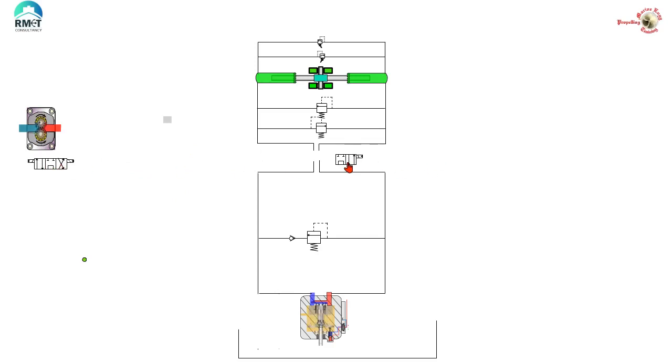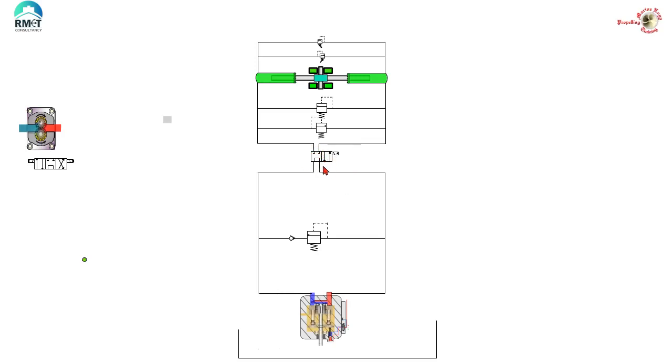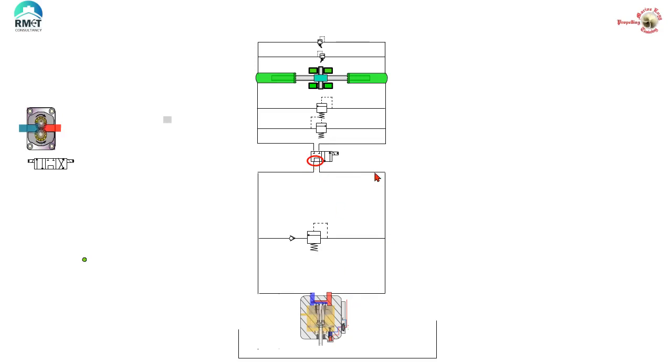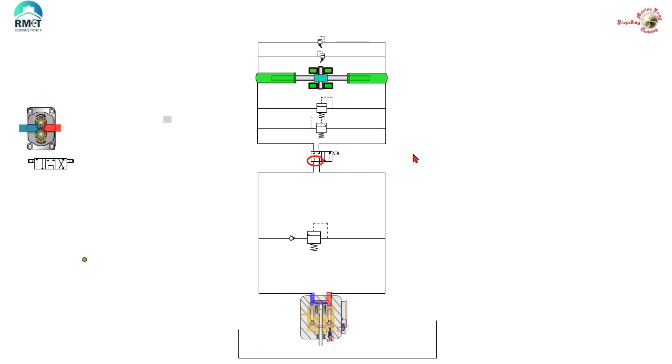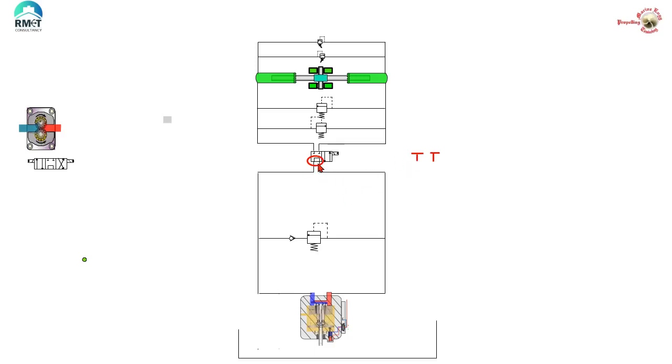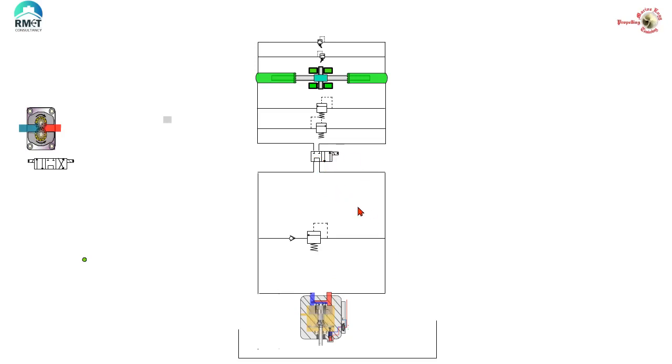But along with this goes the hydraulic lock function. So, I have to put another valve which will continue to give me the hydraulic lock function. I have got back my hydraulic lock function. And you can also see one more thing here. I got an unloading function here. It really does not matter whether I have an unloading function where my oil is short circuiting or going from this side to this side, or I can keep it blocked also. I can keep both the things blocked. Because this being a variable delivery pump, it can go to zero stroke. Now, we have to think what next. How will this valve operate? Obviously, it needs a pilot oil for shifting the spool inside. The solenoid will allow the pilot oil to shift the spool. But I need some pilot oil.